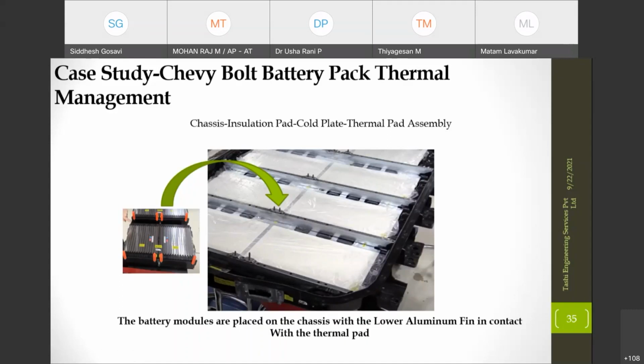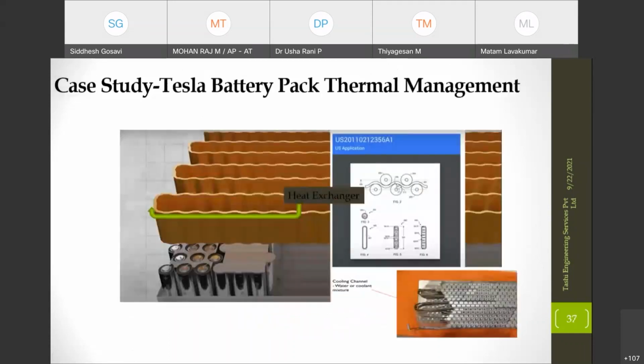So if I have to design the evaporator, the refrigerant line pathways need to be designed such that the temperature non-uniformity inside the cold plate, irrespective of whether the battery is mounted or not, is uniform. And that's why most of the cold plates are manufactured using roll bond, where the material is aluminum. So the temperature gradient is minimum in that case.